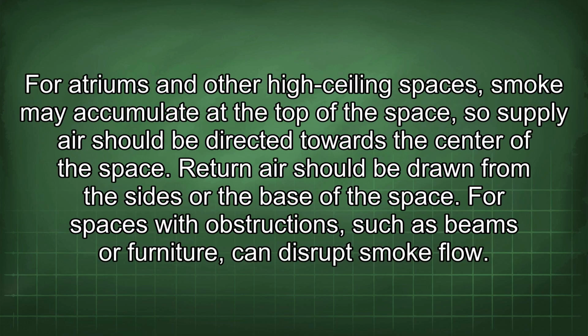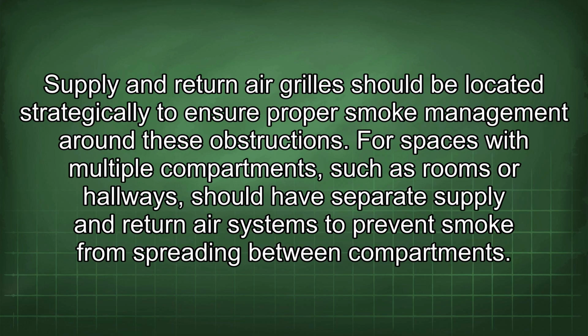For atriums and other high ceiling spaces, smoke may accumulate at the top of the space, so supply air should be directed towards the center of the space. Return air should be drawn from the sides or the base of the space. Obstructions, such as beams or furniture, can disrupt smoke flow. Supply and return air grills should be located strategically to ensure proper smoke management around these obstructions. Spaces with multiple compartments, such as rooms or hallways, should have separate supply and return air systems to prevent smoke from spreading between compartments.